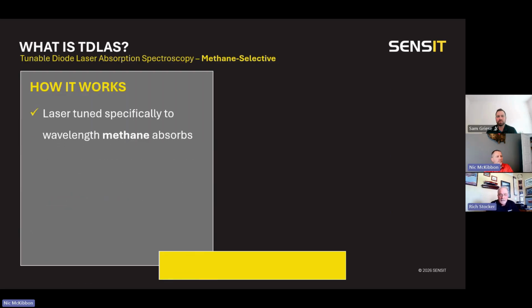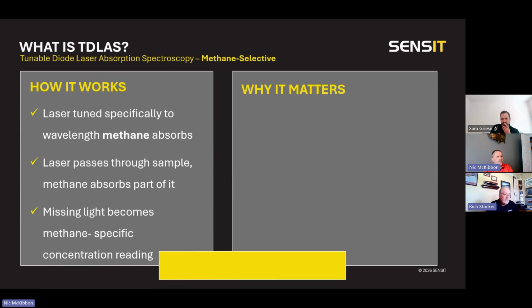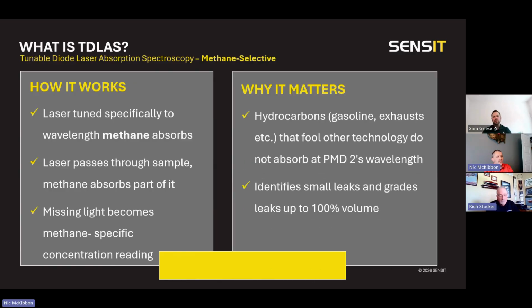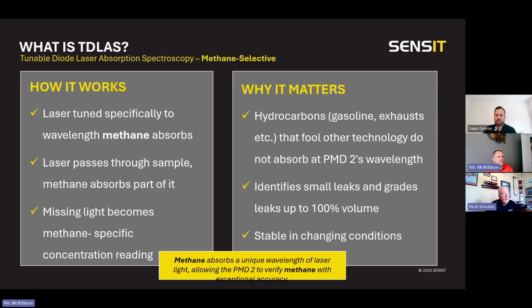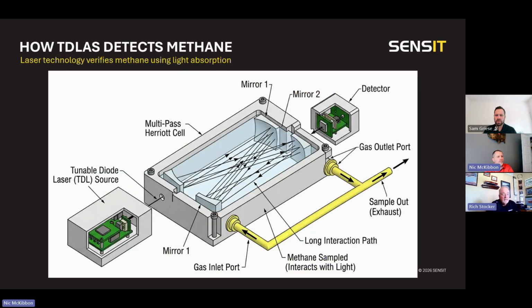So in a 60-second video, we pretty much ran down the basics of how to fire it up, get it ready to use, and shut the unit down. As we talk about the function of that tunable diode laser absorption spectroscopy I mentioned previously, it's tuned to the wavelength of methane. We draw the sample into the instrument itself. The laser passes through that sample, and we have a receiver on the other end that will sense a diminishment of the intensity of the light and interprets that into a gas read.